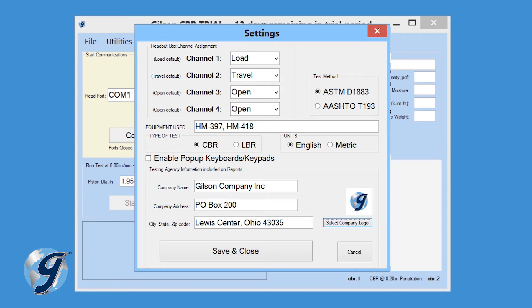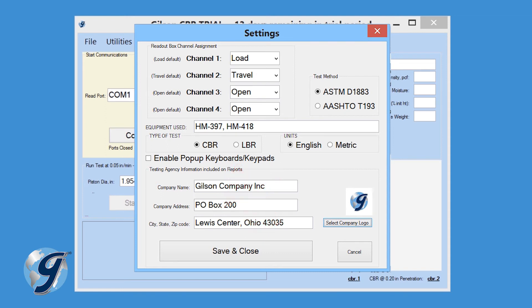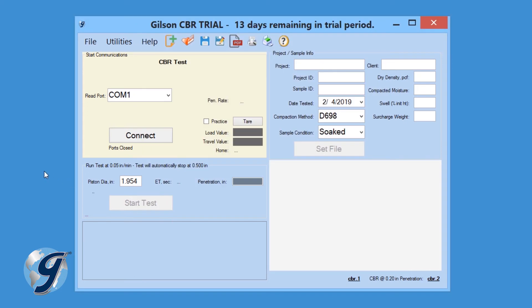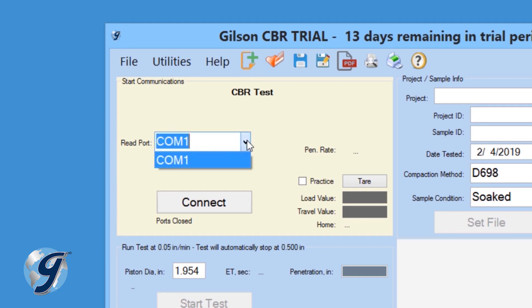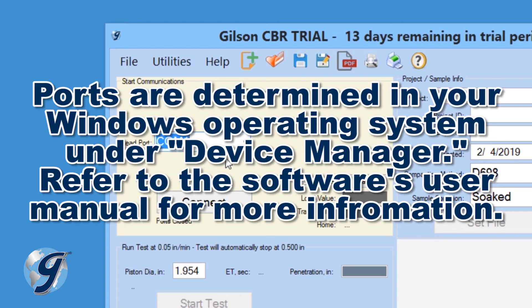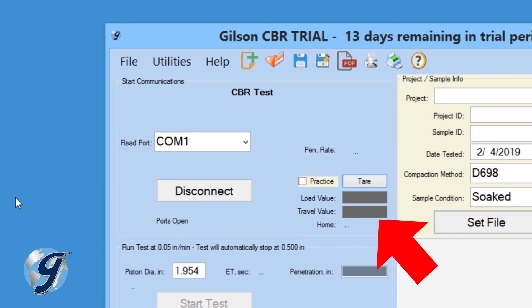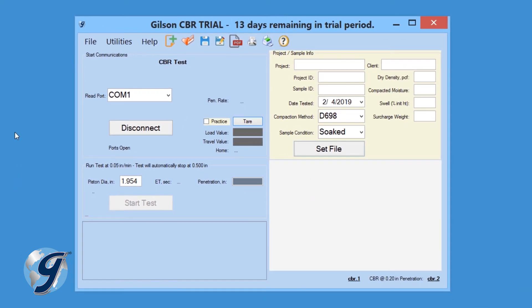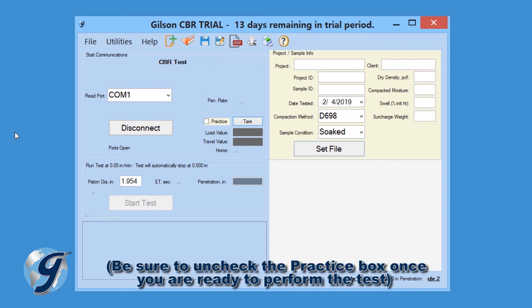Next, select the desired measurement units. If you are using an on-screen keyboard like the one found on a tablet, be sure to enable the pop-up keyboard keypad function. For this demonstration we are using a standard desktop keyboard, so we will leave this box unchecked. Enter the testing agency information that will be included in the test report. Click Save and Close. Now establish your connection to your Readout box by selecting the proper serial port in the Start Communications panel. Once connected, the travel values will be displayed at the bottom right of the Start Communications tile. The LVDT will automatically be tared. Feel free to click on the Practice box to familiarize yourself with the program and its operation. Uncheck the Practice box once you are ready to perform a test.